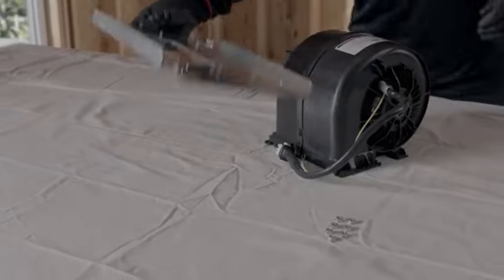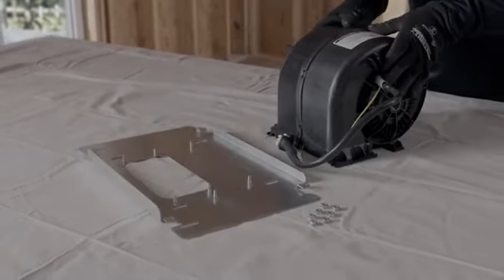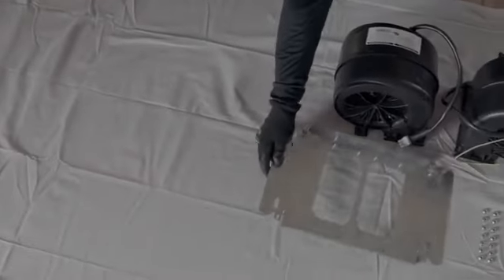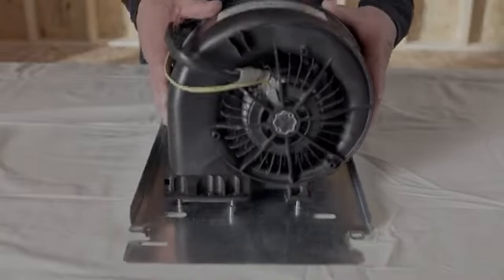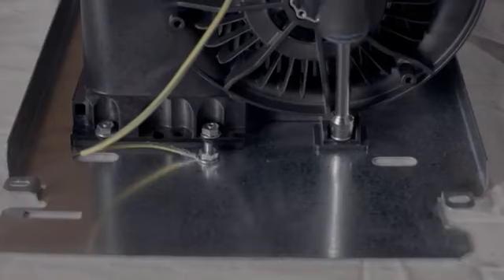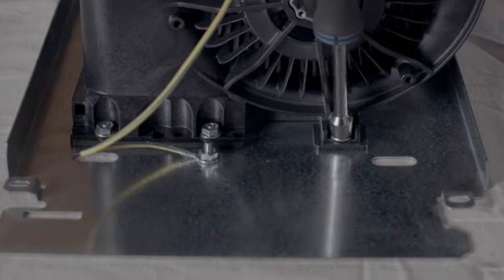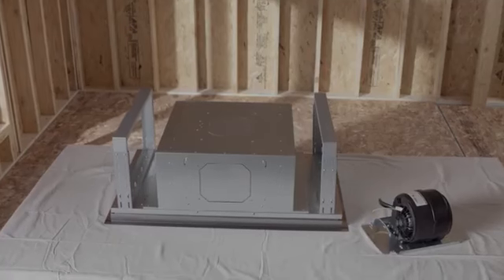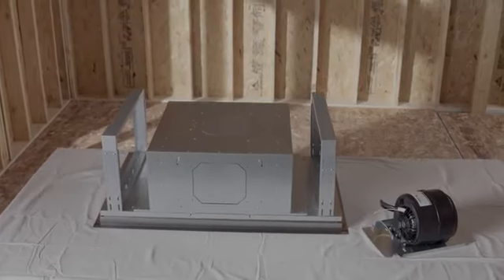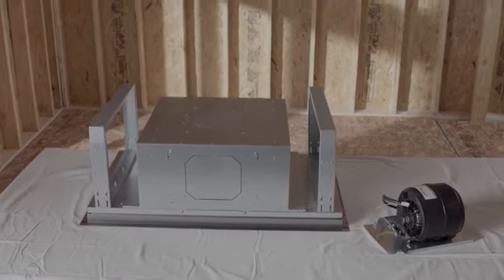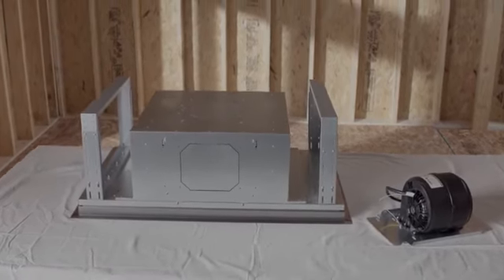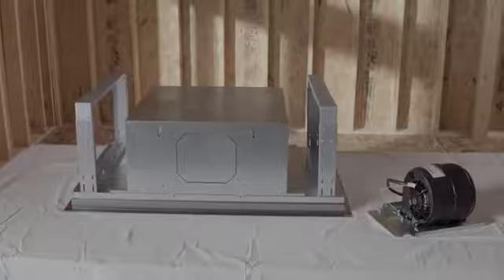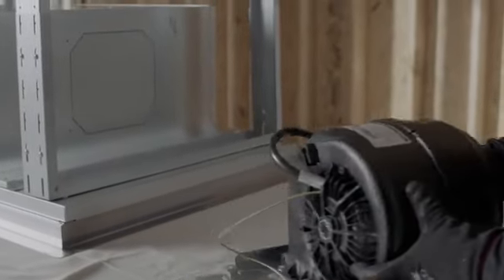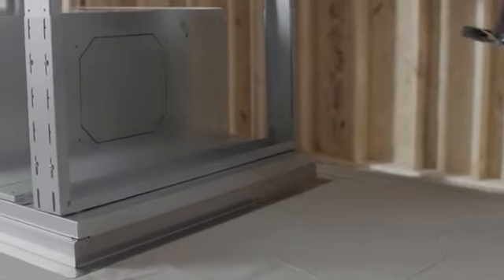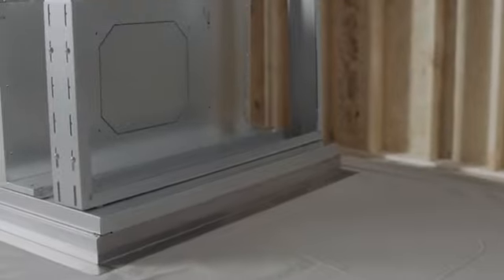The PM6 is a single blower that attaches to this plate. The PM12 is a double blower and attaches to this plate. Attach the desired blower to the plate using the included hex nuts. Once you've selected the desired blower and exhaust position, you can install the blower into the hood. You can do this prior to or after mounting the hood. In this video, we are using the PM6 single internal blower and side exhaust position.